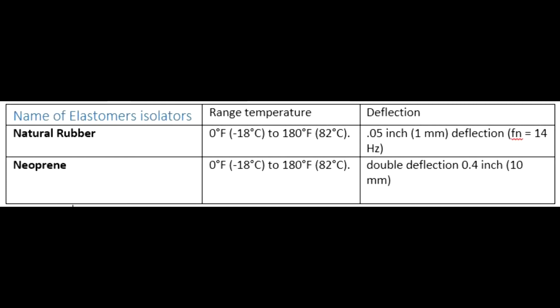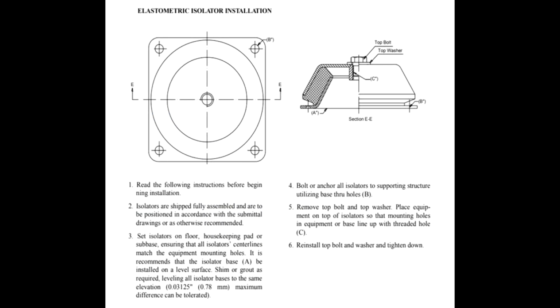Firstly, I am talking about elastomeric isolators. Natural rubber: temperature range 0 degrees Fahrenheit to 180 degrees Fahrenheit or 82 degrees centigrade, and 0.05 inch or 1 mm deflection, frequency 14 Hz. Neoprene isolator: temperature range 0 degrees Fahrenheit to 180 degrees Fahrenheit or 82 degrees centigrade. Double deflection 0.4 inch or 10 mm. Here is the picture of an elastomeric isolator installation system. You can read it very carefully, because if I give the details, this video will be very long. In this picture, here is some data and specification of elastomeric isolators.